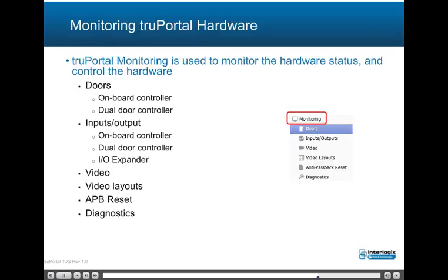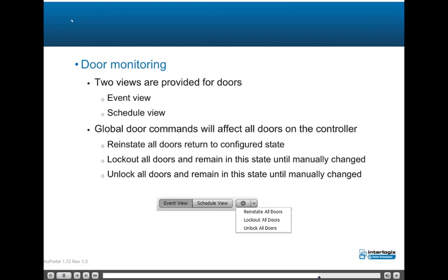TruePortal monitoring is used to monitor the hardware status and control the hardware, including doors (onboard controller and dual door controller), inputs/outputs (onboard controller, dual door controller, and I-O expander), video, video layouts, APB reset, and diagnostics. Door monitoring provides two views: Event View and Schedule View. Global door commands affect all doors on the controller and include reinstate all doors (return to configured state), lock out all doors (remain in this state until manually changed), and unlock all doors (remain in this state until manually changed).